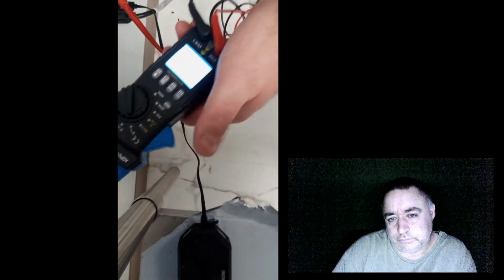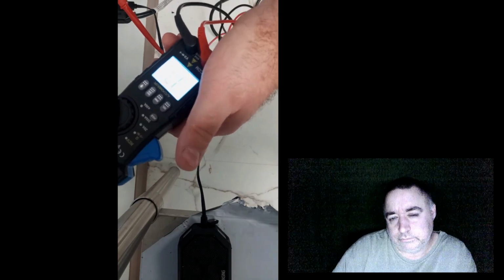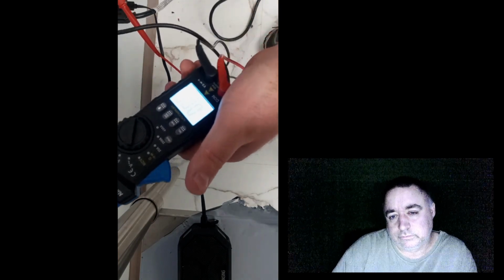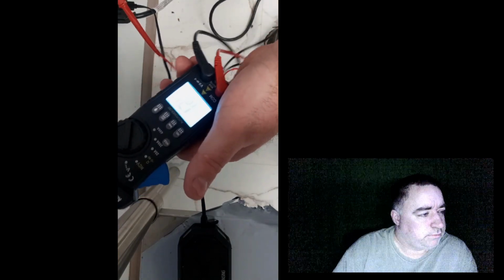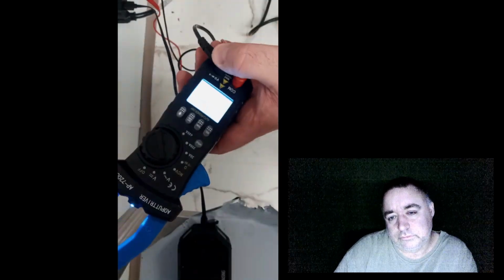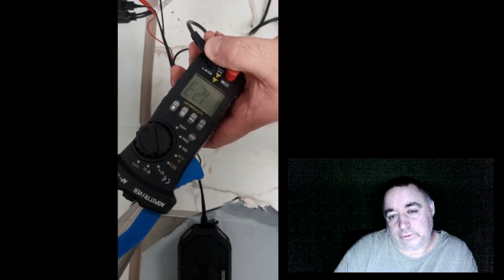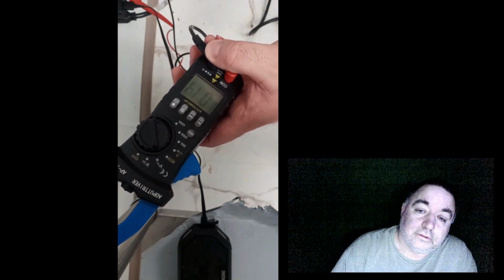Phase 1, 123. Phase 2, 124. Phase 3. So that'll be 360, 363 phase. Unhook it. Ground is good because I'm getting good neutral, getting good ground, getting a good reading on all my hots. You could get bleed over inside that machine. A disconnected outlet. Yeah, pull the plug out with the power turned up. That's kind of dangerous.